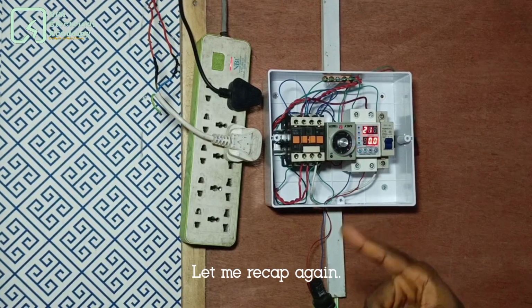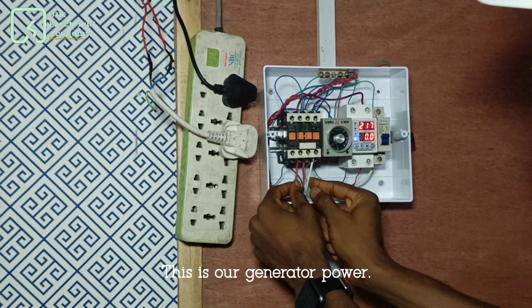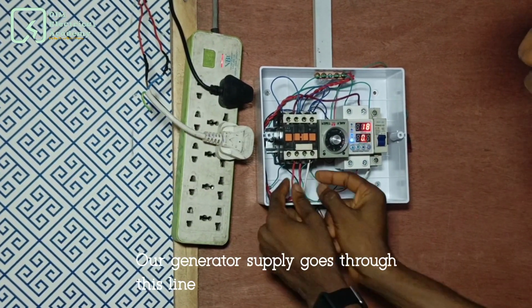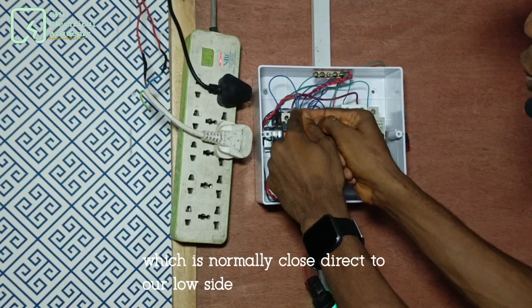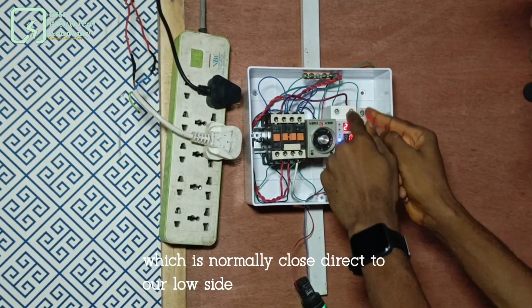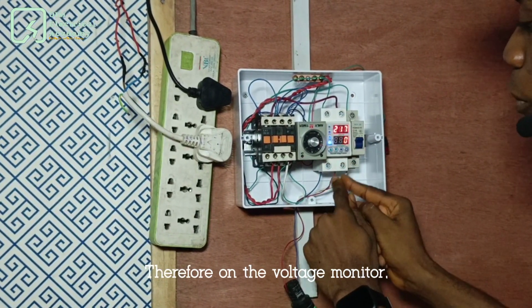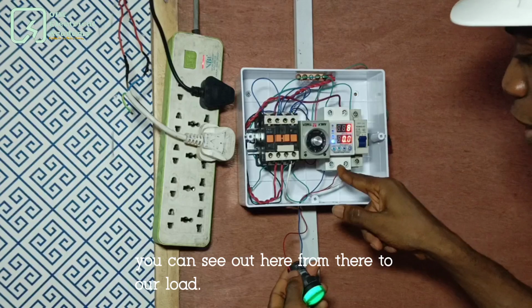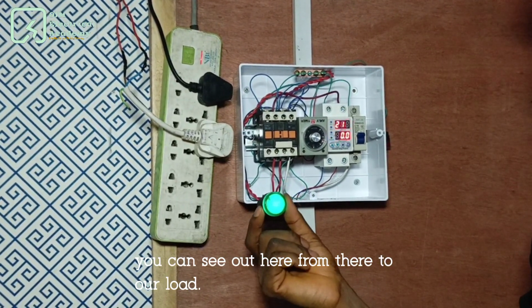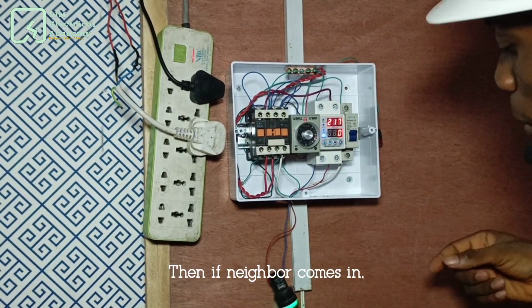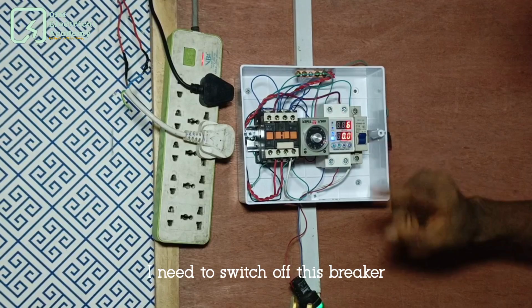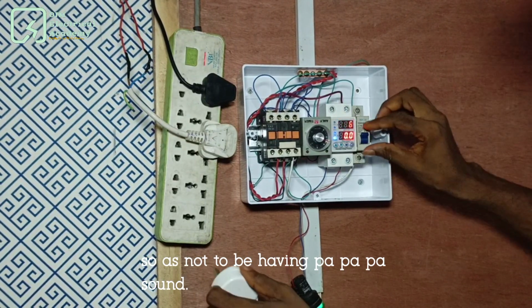Let me recap again. This is our generator power. Our generator supply goes through this line, which is normally closed, direct to our load side, which is on the voltage monitor. Then from the voltage monitor, you can see out here, from there to our load. Then if NEPA comes in, I need to switch up this breaker so as not to be having the alarm sound.